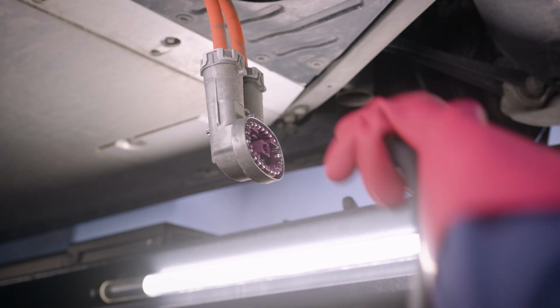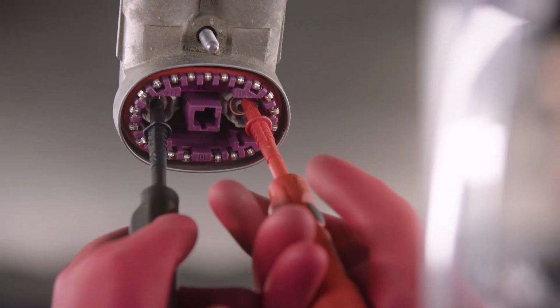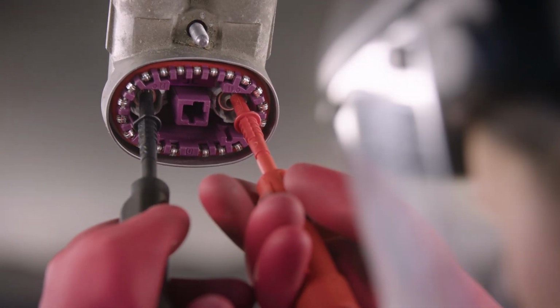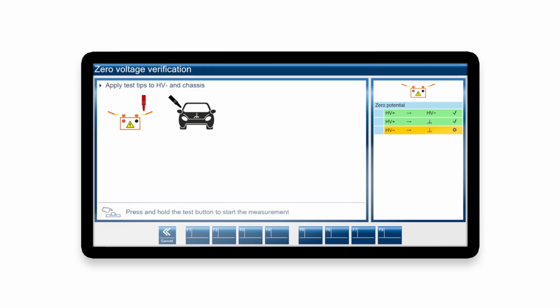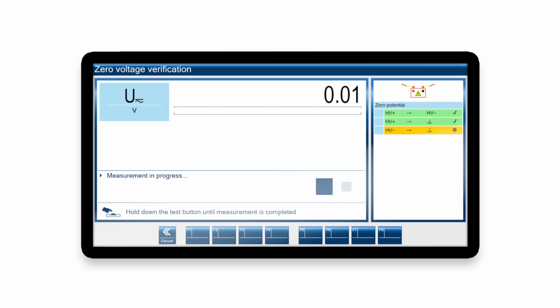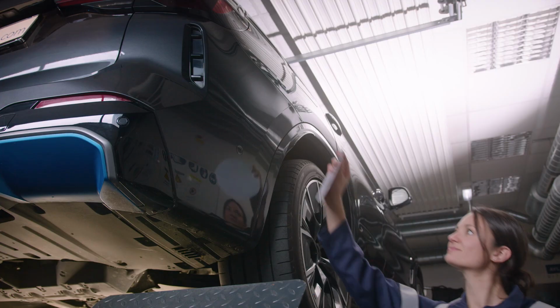Even with thick safety gloves, you can easily operate the workSAFE via the button on the probe. Follow the steps shown in the guided software. If there are any residual voltages in the system, they are actively discharged by workSAFE during the measurement. All your measurement results are automatically documented in a protocol.